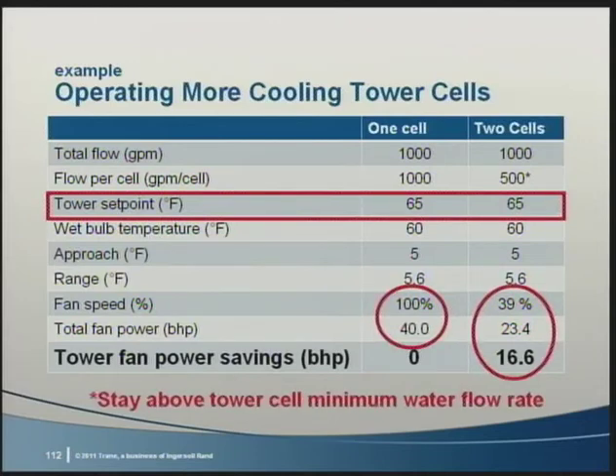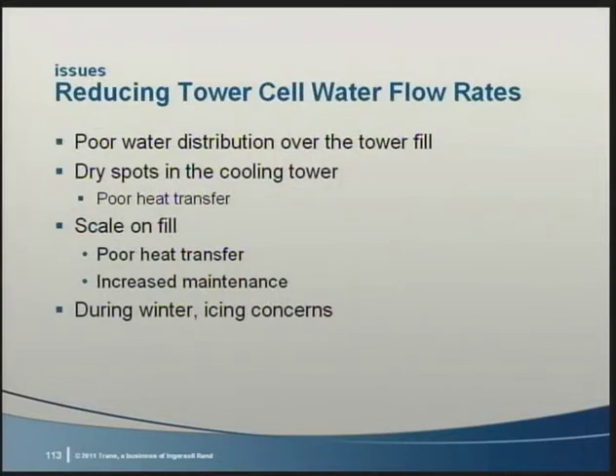But remember that the water flow over each cell must stay above the minimum flow rate required by the tower provider. What happens if the flow rate drops too much? As the water flow drops, there comes a point that the tower design does not distribute the water evenly throughout the fill. This can lead to dry spots in the cooling tower. Since the pressure drop through the dry fill is lower than through the wet fill, more air will flow through that dry area and the heat transfer will be reduced. In addition, scale can form on areas of the tower fill experiencing reduced flow. This again leads to poor heat transfer and increased maintenance. In extreme conditions, icing can occur on cooling towers.